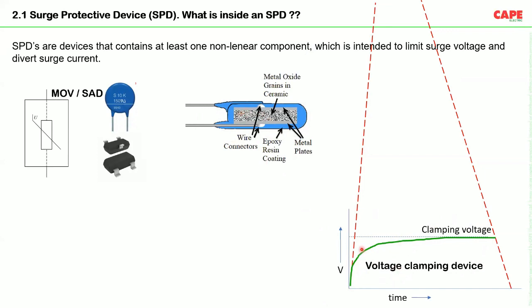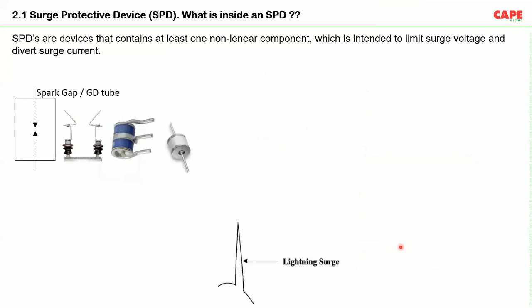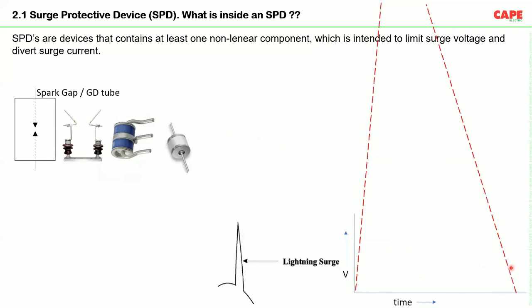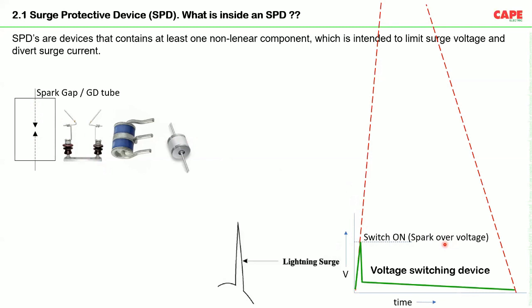voltage clamping type devices. So a metal oxide varistor is clamping the voltage. It is not allowing the voltage to go beyond a certain level between its terminals, and these are called voltage clamping type devices. Similarly, there is another device called a voltage switching device. Examples are spark gaps, GD tubes, horn gaps, and so on. These devices operate with different characteristics. Say, for example, you have the transient over voltage, where, as I said, the maximum limit is unknown. These devices will work like a switch. Under normal condition the switch is off, and whenever the potential difference reaches the voltage protection level or spark over voltage of that particular device, the switch is on. As a result, your line and neutral, for example, are short circuited. So these devices are called voltage switching type devices.